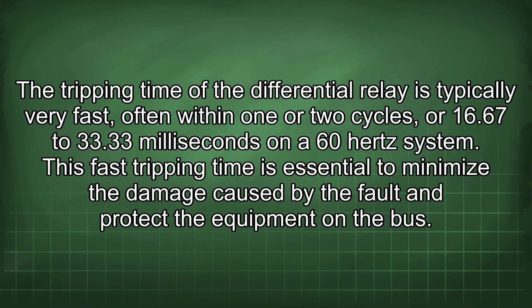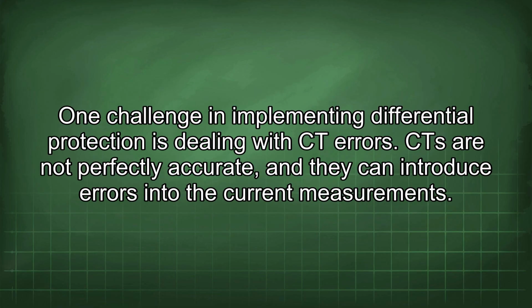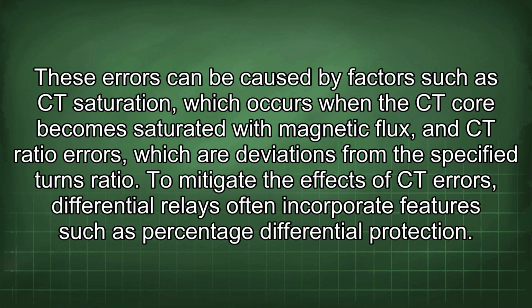This fast tripping time is essential to minimize the damage caused by the fault and protect the equipment on the bus. One challenge in implementing differential protection is dealing with CT errors. CTs are not perfectly accurate, and they can introduce errors into the current measurements. These errors can be caused by factors such as CT saturation, which occurs when the CT core becomes saturated with magnetic flux, and CT ratio errors, which are deviations from the specified turns ratio.